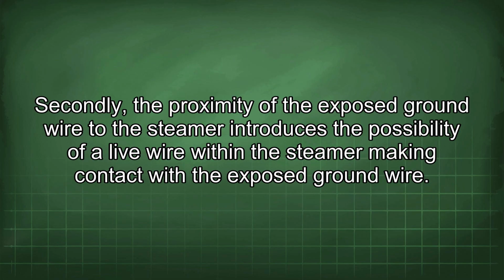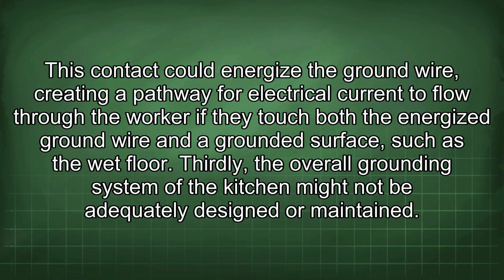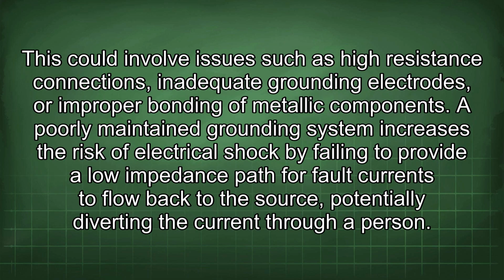Secondly, the proximity of the exposed ground wire to the steamer introduces the possibility of a live wire within the steamer making contact with the exposed ground wire. This contact can energize the ground wire, creating a pathway for electrical current to flow through the worker if they touch both the energized ground wire and a grounded surface, such as the wet floor. Thirdly, the overall grounding system of the kitchen might not be adequately designed or maintained. This could involve issues such as high resistance connections, inadequate grounding electrodes, or improper bonding of metallic components. A poorly maintained grounding system increases the risk of electrical shock by failing to provide a low impedance path for fault currents to flow back to the source, potentially diverting the current through a person.